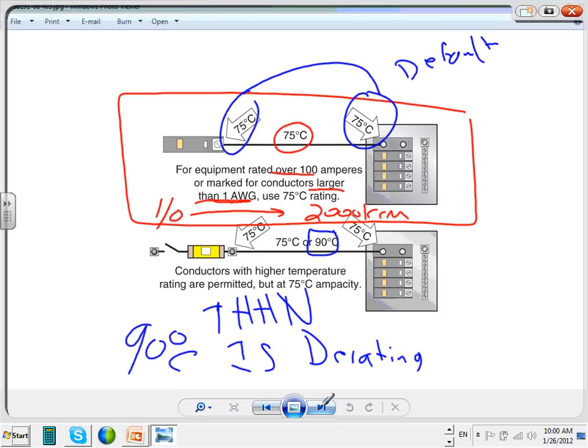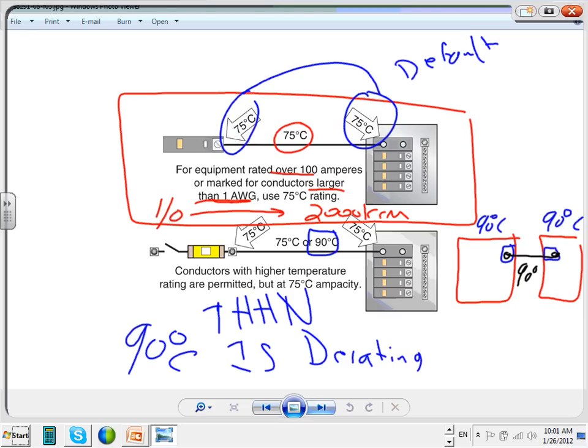Now, for those of you who are going to be designers one day, take medium voltage. If you have a medium voltage piece of equipment and between two pieces of equipment the lugs are rated here at 90 degrees Celsius, and I am to use a cable between them that is a 90-degree cable, and this is 13.8 kilovolt, a medium voltage, or so-called over 600 volt system. Look at this. The code allows you to size based on 90 degrees, completely different. And I know we did a transformer based on this. So remember, this is for medium voltage.